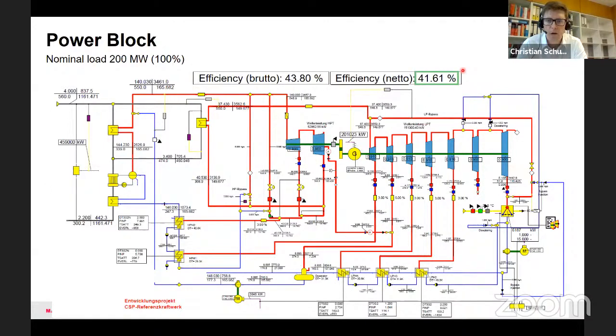I mentioned it already, we have also a good part load behavior, so we only have a pressure drop of 2%. That means at 50% we have 39.2% efficiency. The reason therefore is that the power of the ACC can be reduced by speed control, and that leads to the high efficiency. The minimum load of the turbine is 25%, so also here we can go very deep.